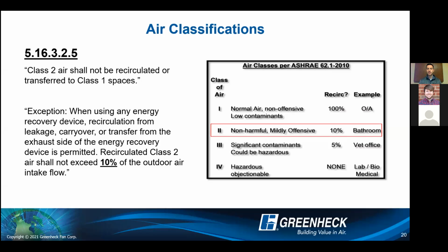And then class 4 is actually your hazardous, objectionable type gases, fumes, lab exhaust type systems, maybe biomedical type applications where no recirculation, absolutely 0% cross contamination is allowed. And the reason I want to walk through this is if you can think about that last slide, I said 3 to 5% cross contamination. Well, technically class 1 through 3, you're completely fine to utilize that energy recovery wheel as is without a purge. And class 4, you can't use any.